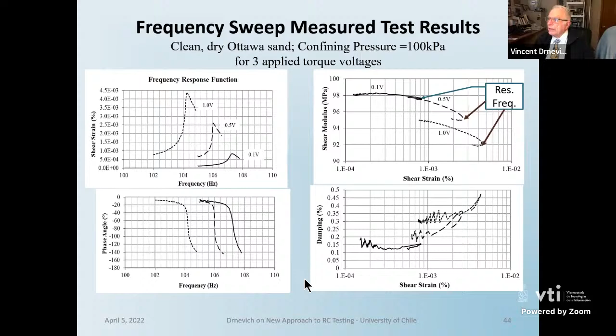So this test runs automatically. We set it up, we start it at the high frequency, let's say, and set go, and we sit back and watch. The analyzer will stop at each frequency and wait, cycling a number of cycles to let the system settle at that frequency. We then take a certain number of cycles afterwards to get the data, and then we move to the next frequency and continue doing that. It takes about 20 minutes to get 200 data points for each curve. It's done all automatically. Those data are downloaded and then processed by a spreadsheet program to get the shear modulus and damping for each strain.